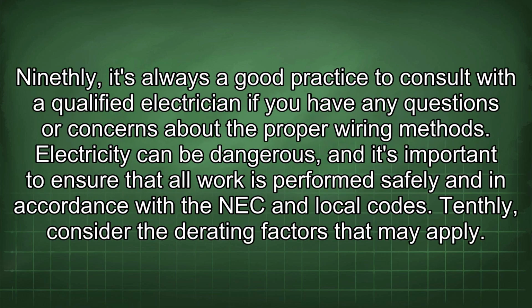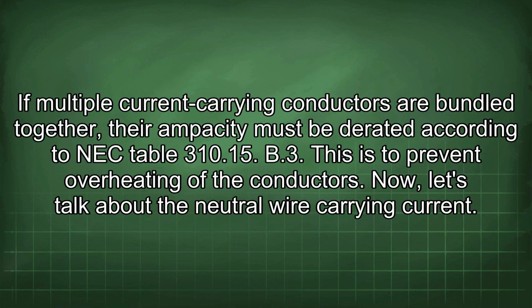Ninthly, it's always a good practice to consult with a qualified electrician if you have any questions or concerns about the proper wiring methods. Electricity can be dangerous, and it's important to ensure that all work is performed safely and in accordance with the NEC and local codes. Tenthly, consider the derating factors that may apply. If multiple current-carrying conductors are bundled together, their ampacity must be derated according to NEC Table 310.15(B)(3). This is to prevent overheating of the conductors.